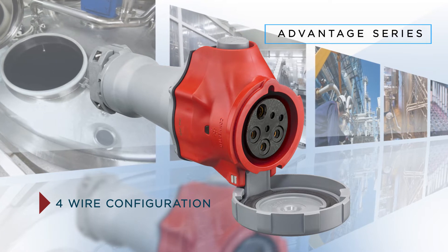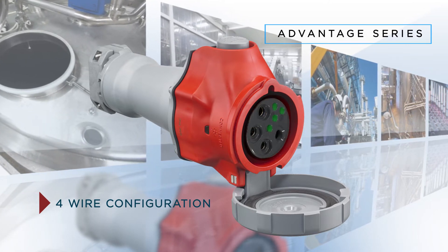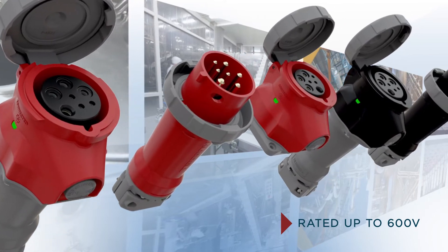Besides the control circuit functionality, these devices are available in a four-wire configuration with three additional auxiliary contacts for 30-amp versions, as well as four auxiliary contacts for 60-amp versions. Finally, these devices are similarly rated up to 600 volts.